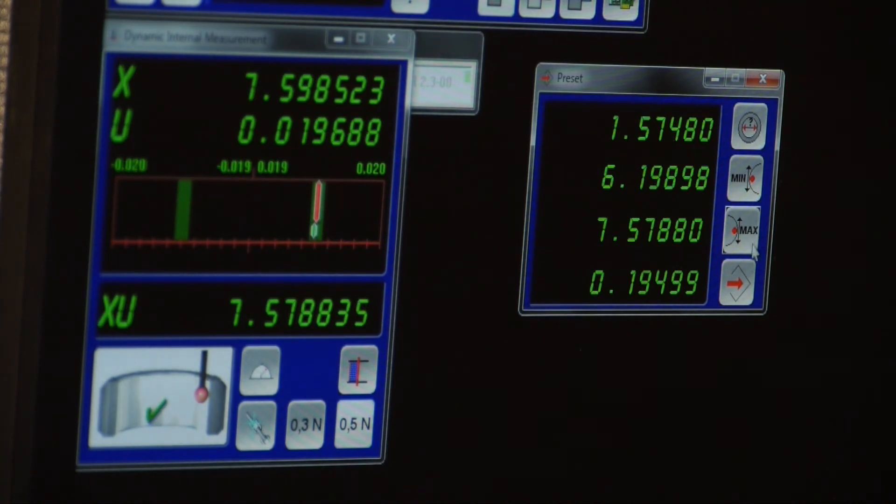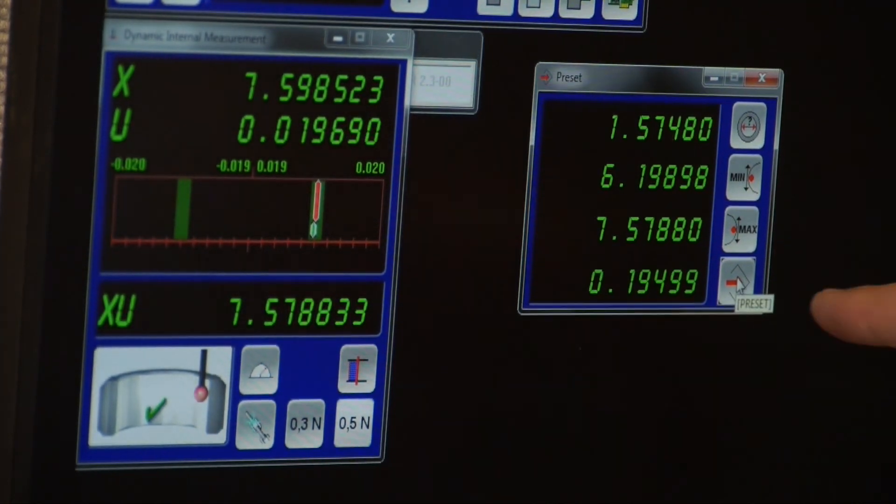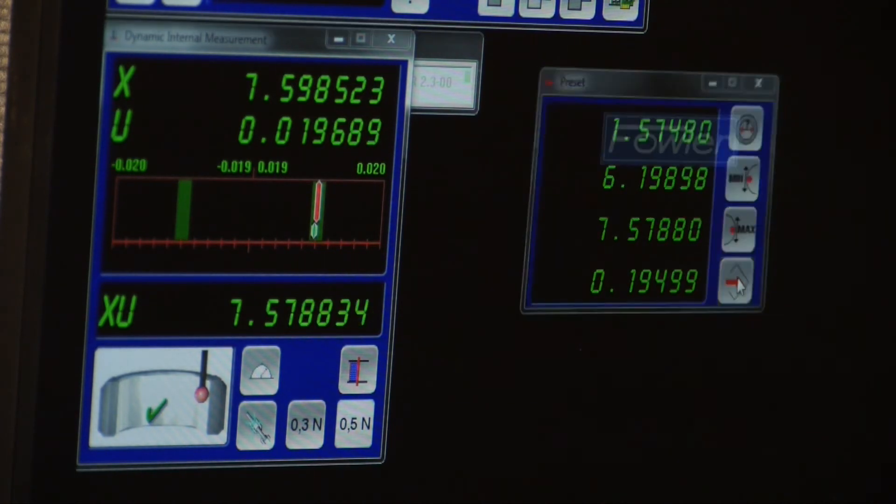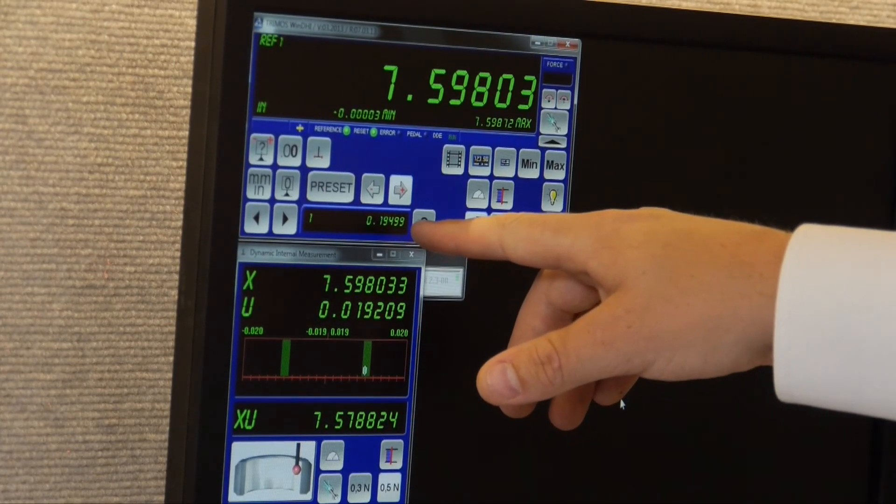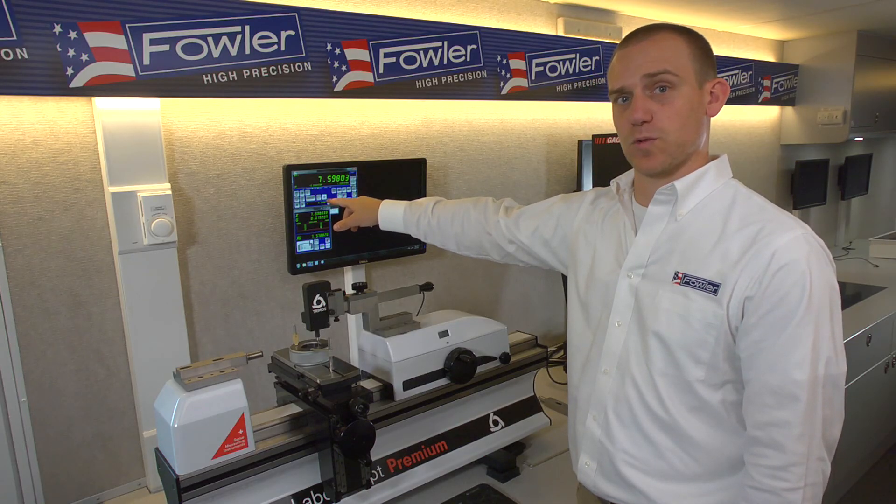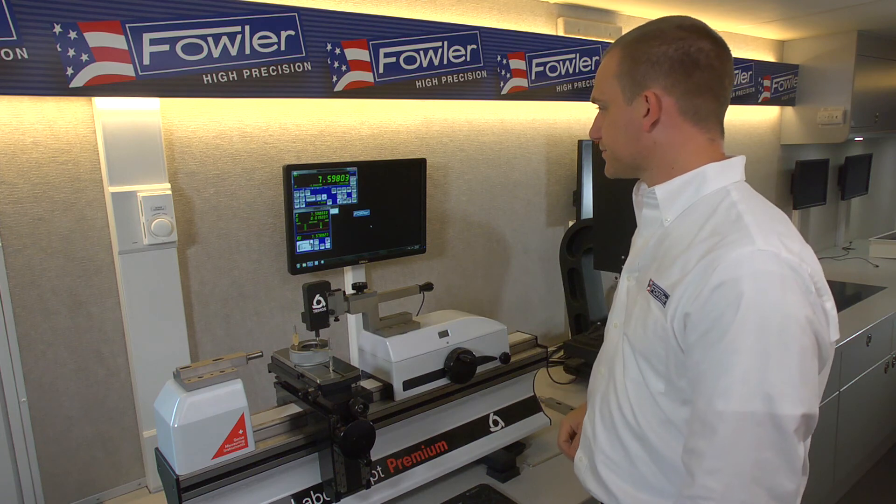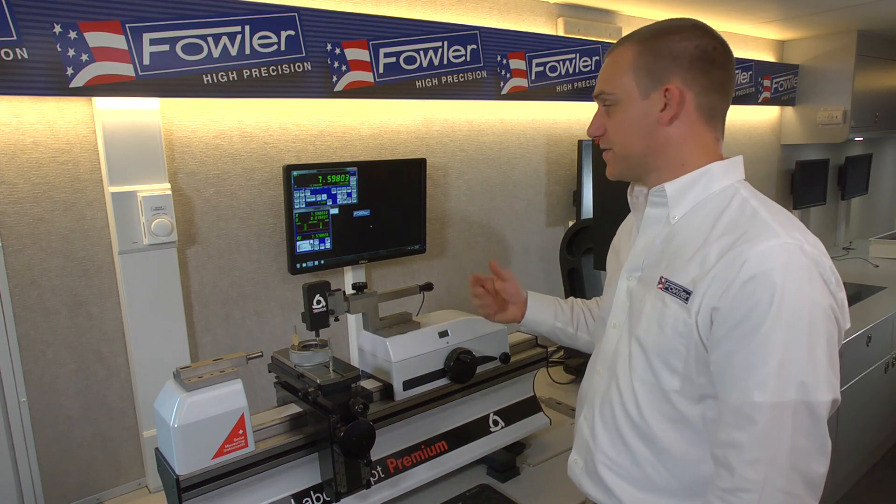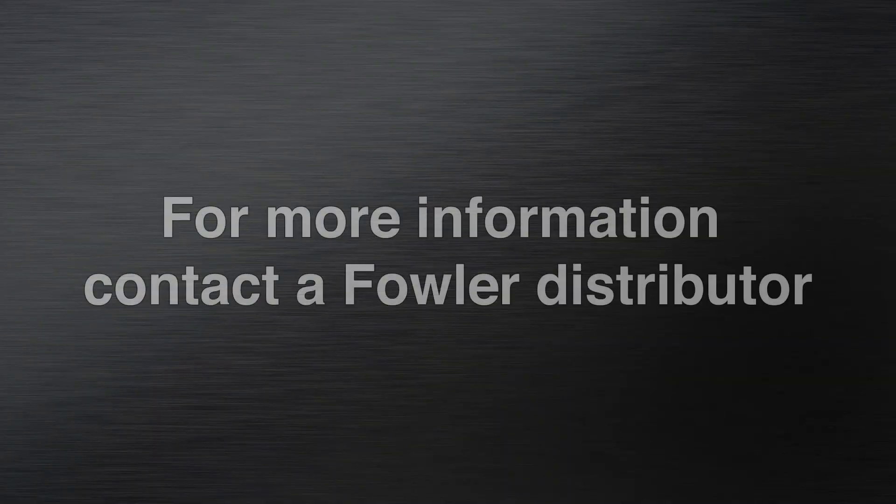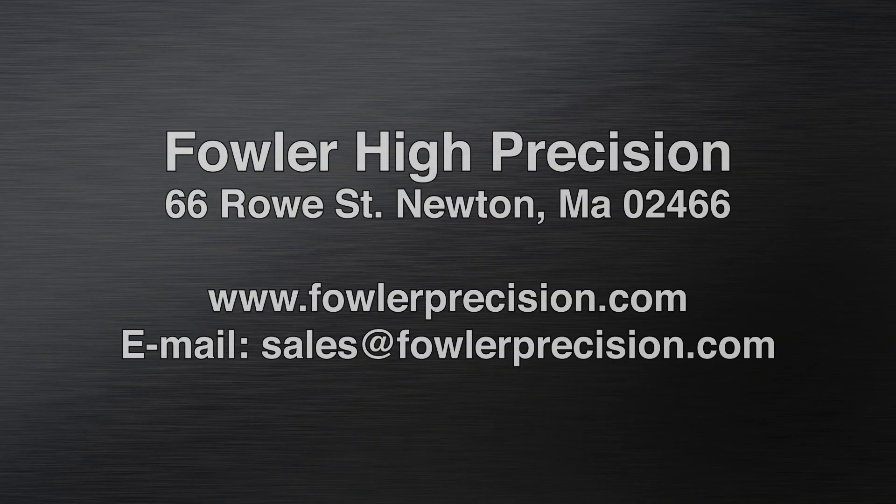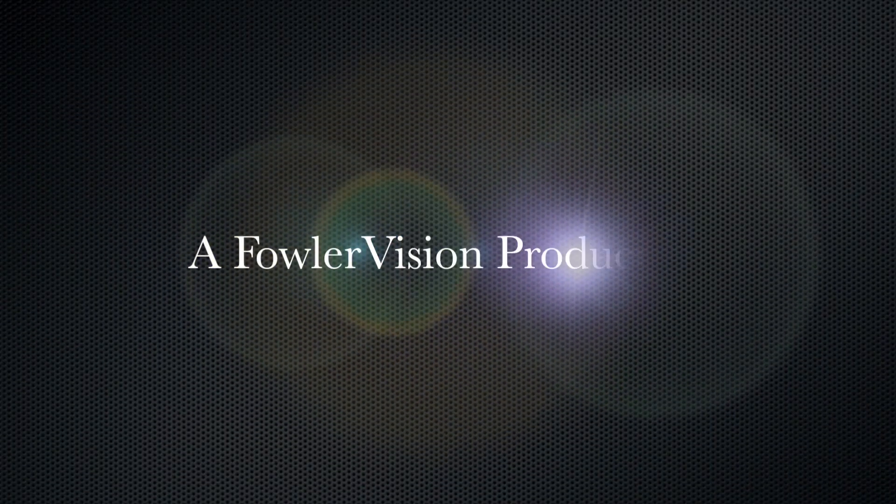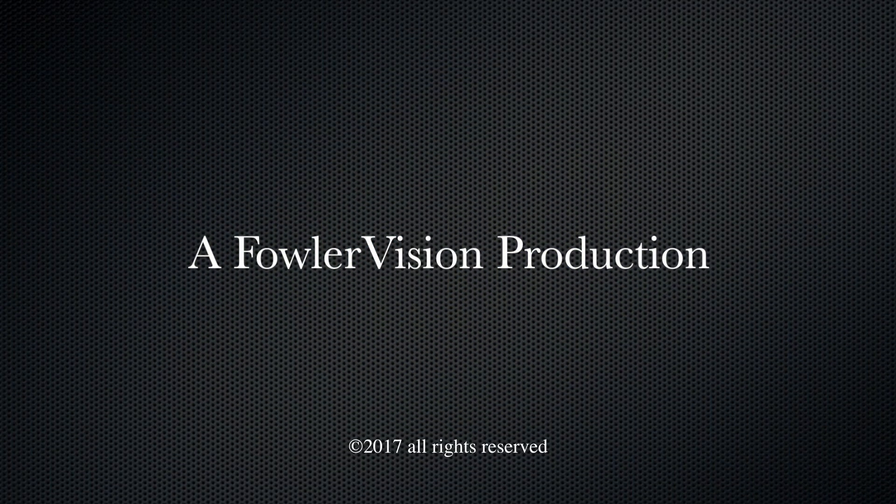So if we come down and hit the bottom right button here, you get a little pop-up that says preset. That will take that value and lock it in as our preset value. So that locks it in as preset number one. Once we have our probe constant locked in as a preset, now we can measure a ring.